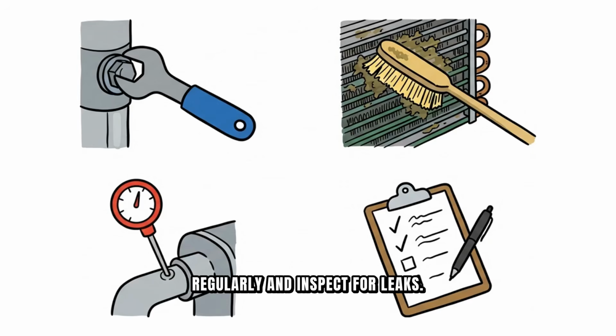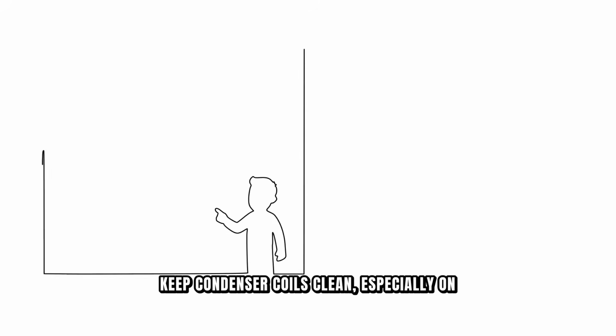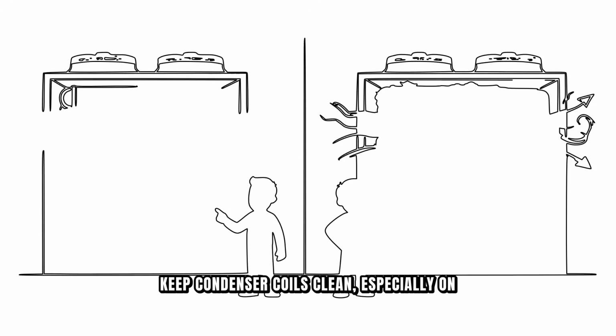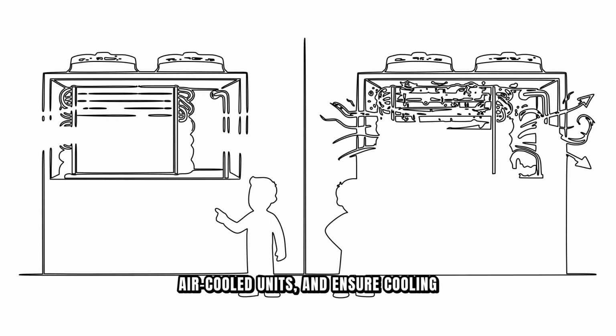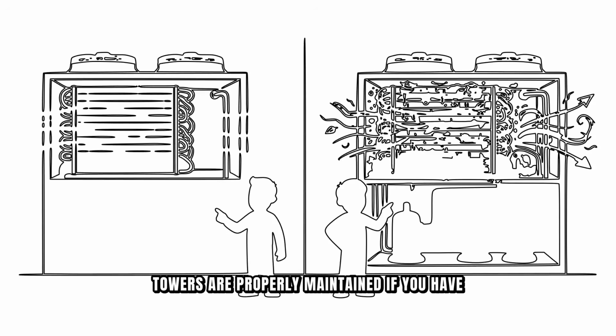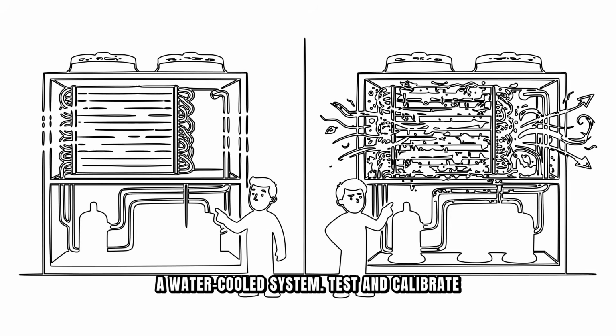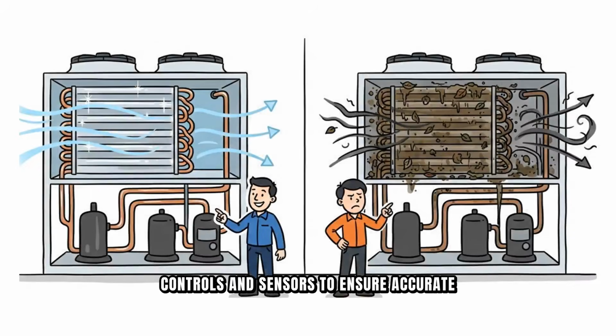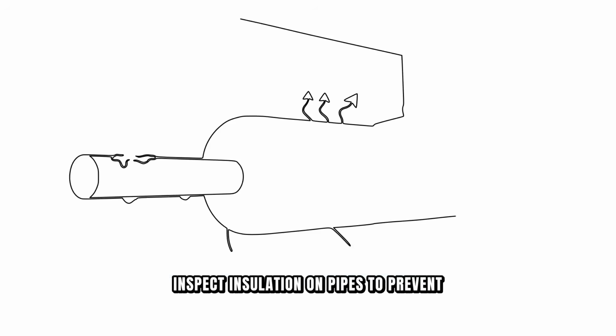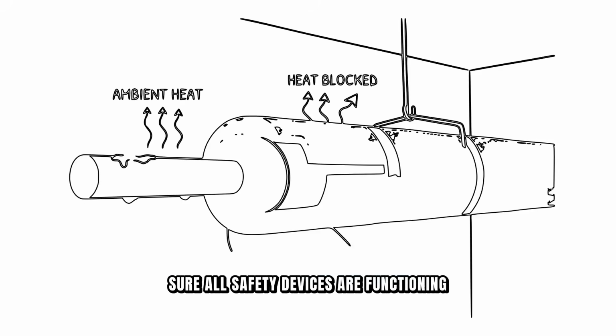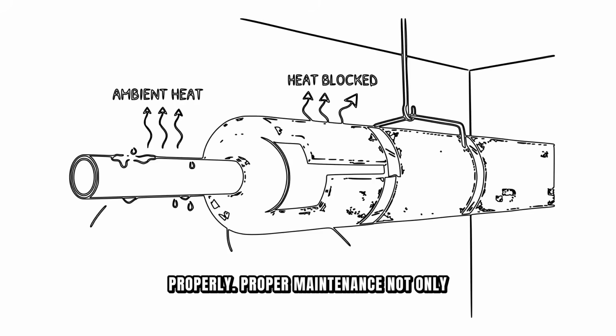Check refrigerant levels regularly and inspect for leaks. Keep condenser coils clean, especially on air-cooled units. And ensure cooling towers are properly maintained if you have a water-cooled system. Test and calibrate controls and sensors to ensure accurate temperature control. Check all electrical connections for corrosion or looseness. Inspect insulation on pipes to prevent heat gain and condensation issues. Make sure all safety devices are functioning properly.